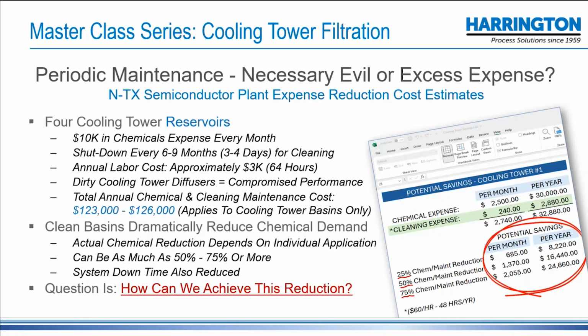And so when you have a clean cooling tower, you're going to use less chemicals. A lot of times, a lot of the chemicals that are injected in the cooling towers go straight into the sludge layer at the base of the unit. They're not doing anything other than being absorbed by the sludge and even the organics within the tower, but they're not doing their stated purpose. You're feeding the dirt. And so if you take that out of the equation, you can have savings of, well, I say between 50 and 75%. And let's keep it there just for example's sake. I've seen reductions as much as 90% in the field.